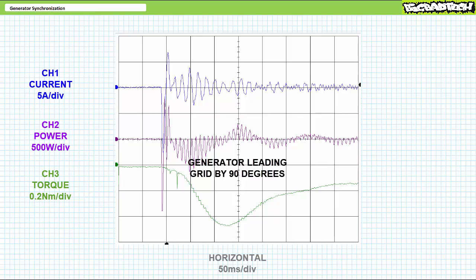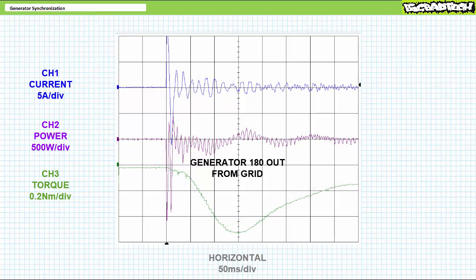Are we done torturing this machine? Not remotely. What's the worst possible mismatch you could imagine? 180 degrees? Yeah, let's do it. If this thing breaks, it's your fault. Given the rotor is totally opposite the stator, it'll be a 50-50 chance if it acts like a motor or generator. Bam. Oh, this is bad. When I close the contactor, the machine makes this awful sound like it's getting dragged through a knot hole backwards. Looks like we're deep in generator mode with the grid aggressively braking the rotor backwards and a massive spike of electrical current and power. It's probably the worst thing that could happen — if this is a large expensive machine, you might be picking up the pieces and looking for a new job. In summary, do not try this at home.